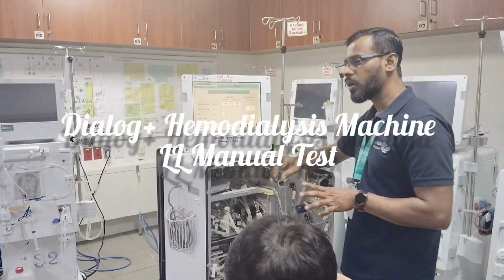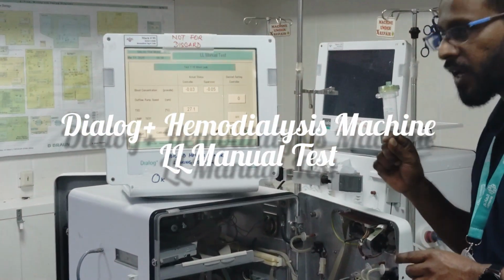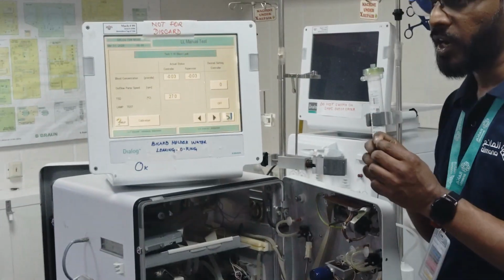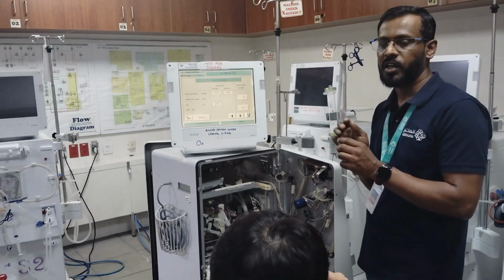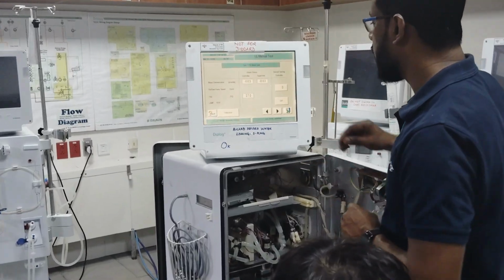Source of the controller and supervisor of the blood leak. If you pass anything red color inside the machine, it will try to detect it. Especially for the blood, it's trying to detect the blood. That's why we call it blood leak detector.